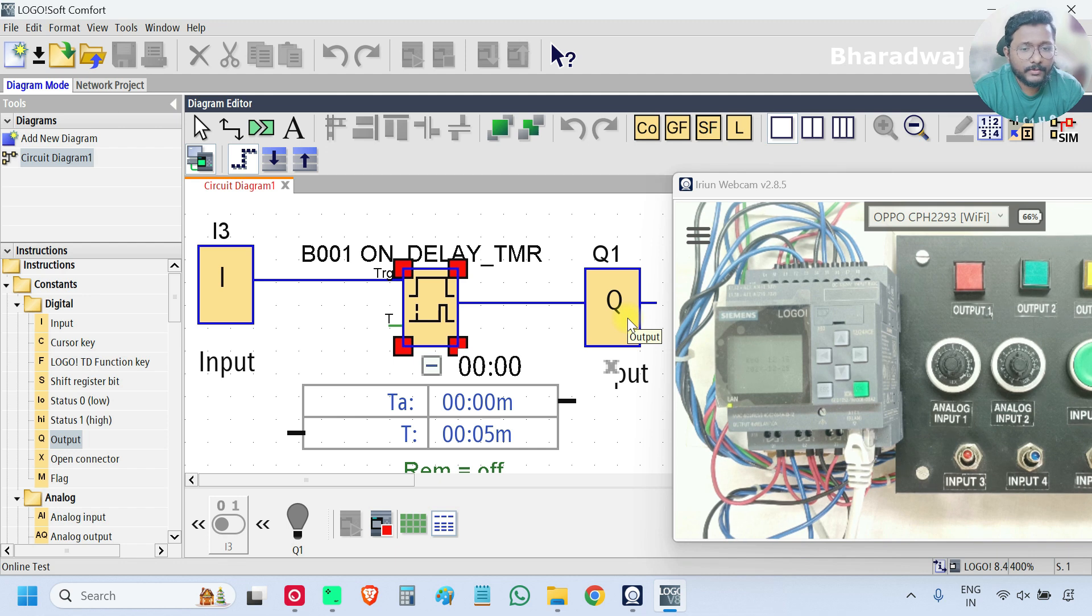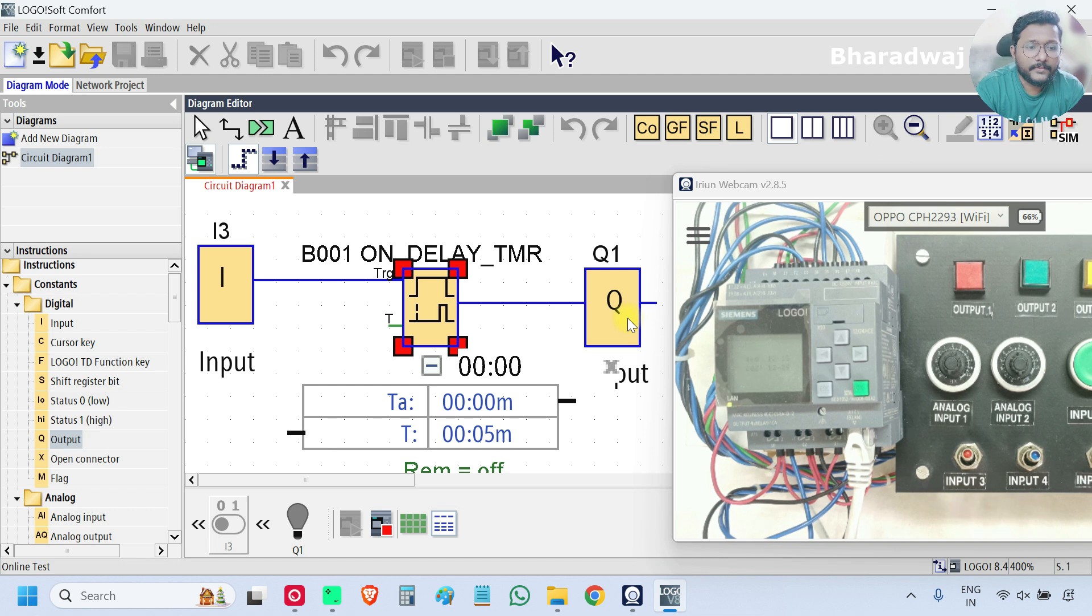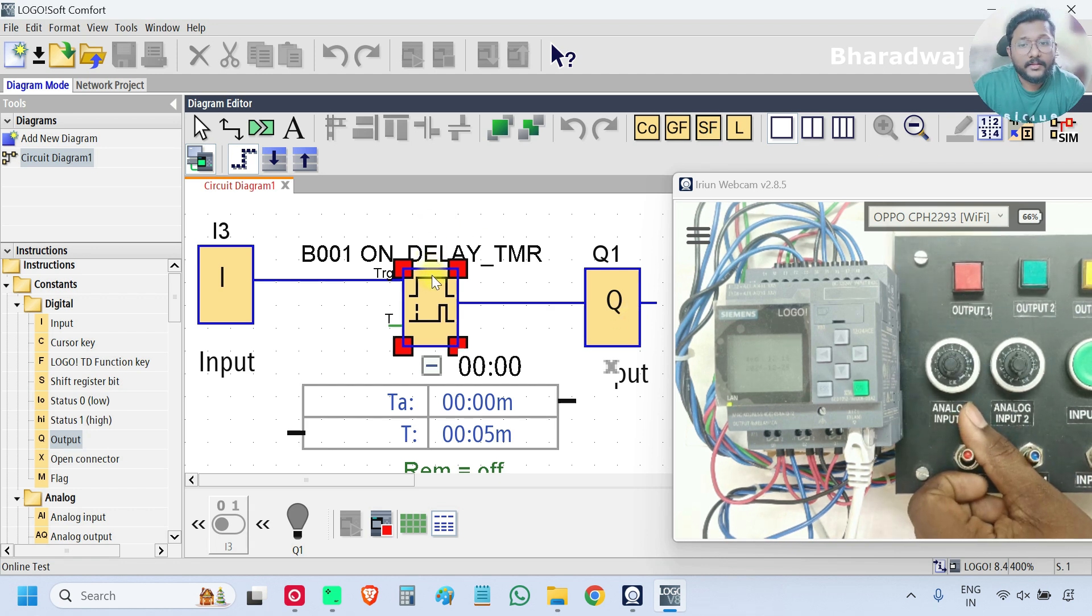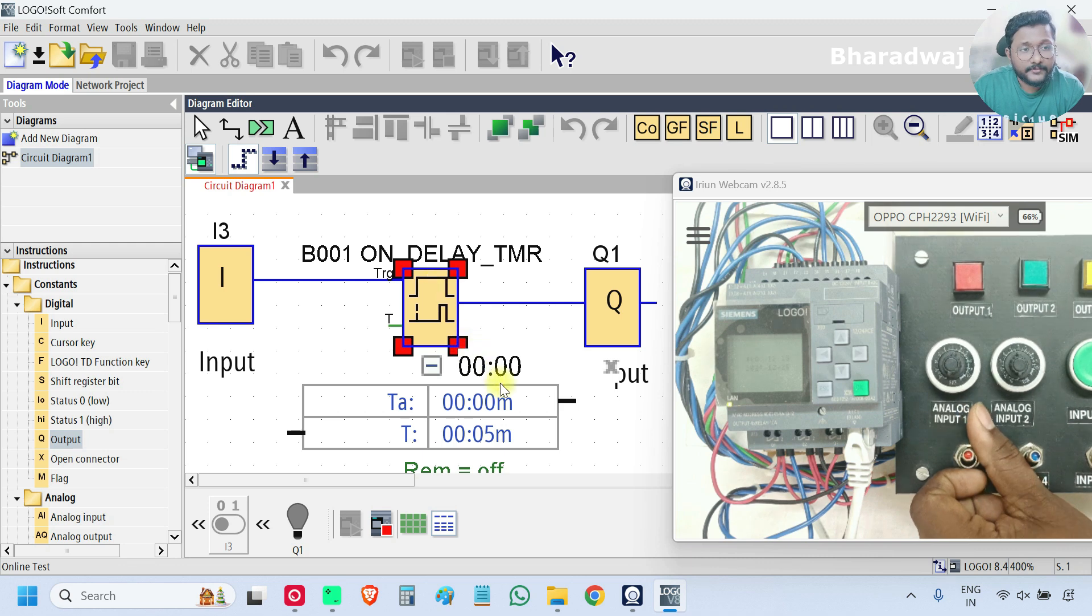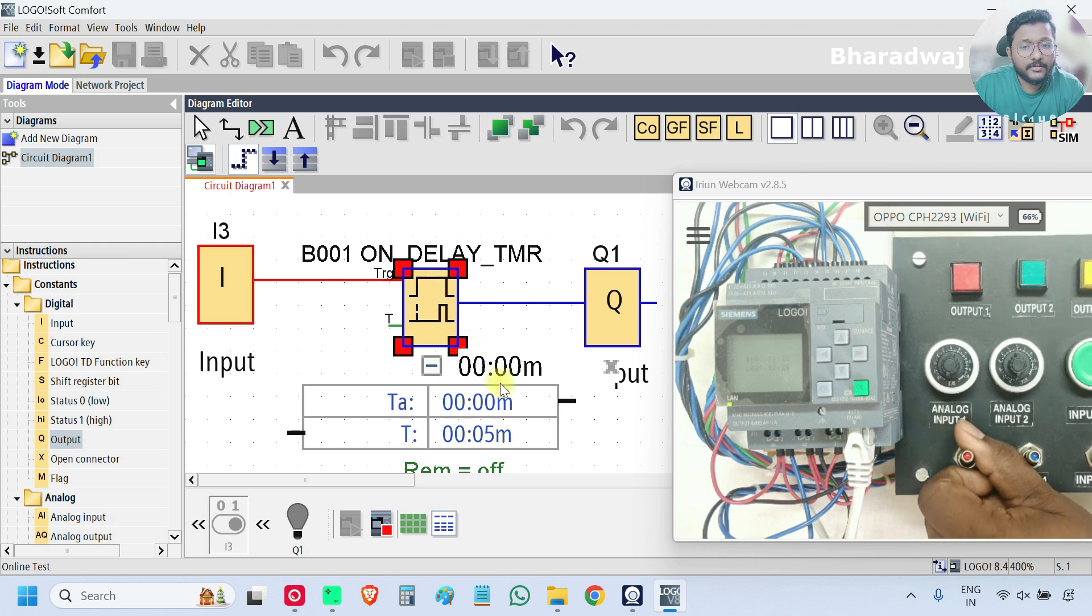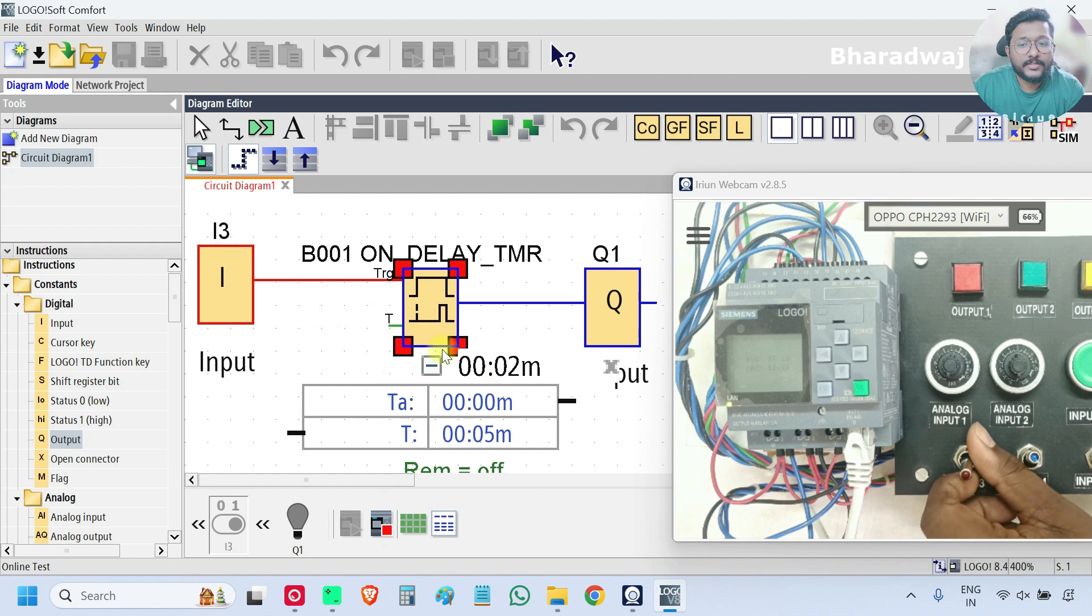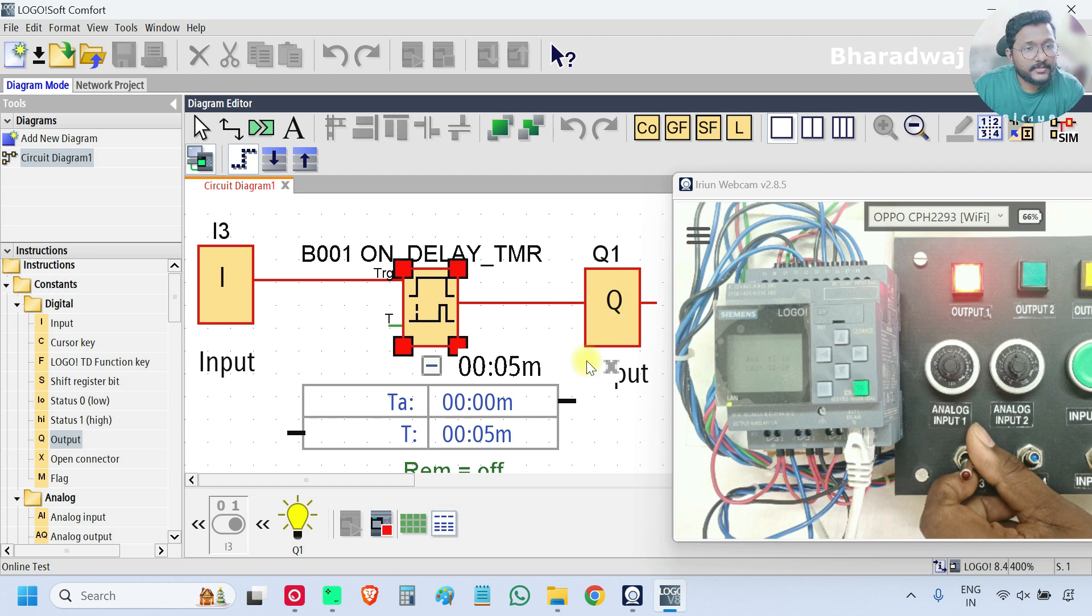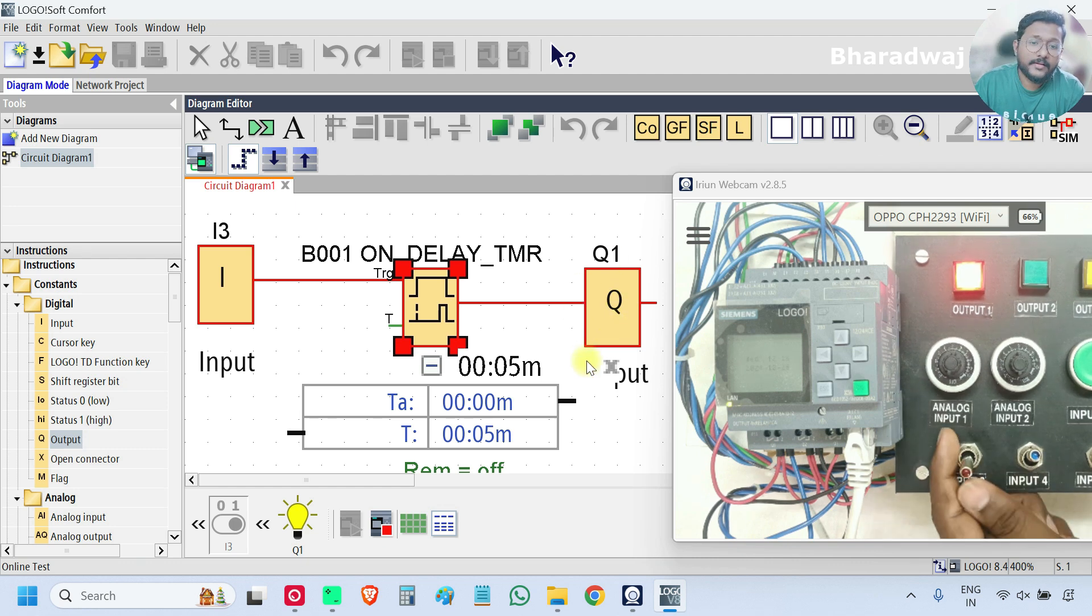We will test the logic now. So now the input is off. I will turn on the input. Then immediately the timer will be started. Observe. Input is on. Timer started. Whenever it reaches 5, then output is on. So what is happening here?